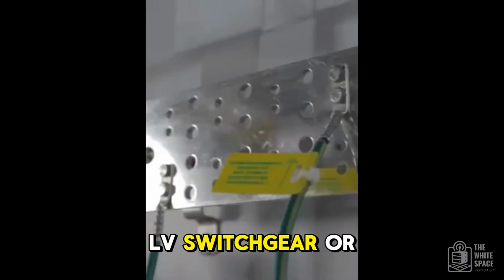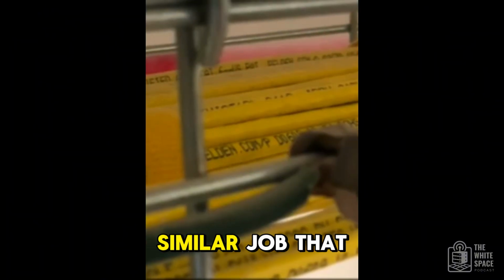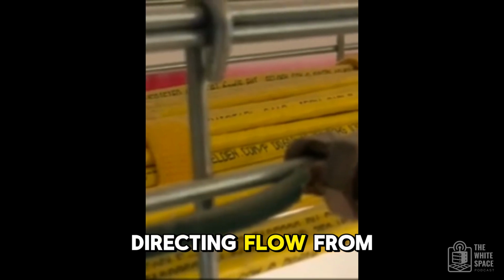And for smaller facilities, under a megawatt, you're usually looking at low voltage switchgear, LV switchgear, or maybe switchboards. They do a similar job but handle lower power levels, directing flow from the transformers or generators to the servers, the cooling, and so on.